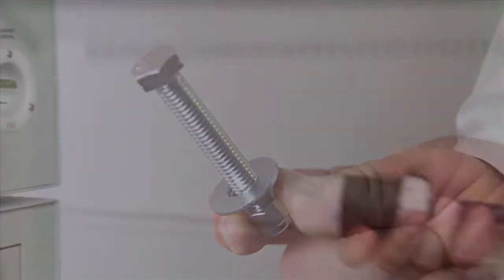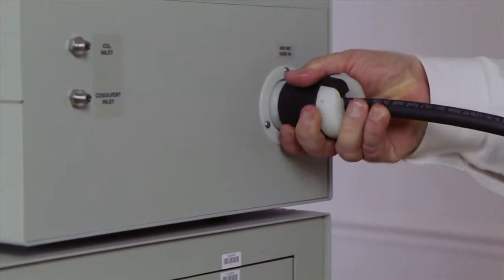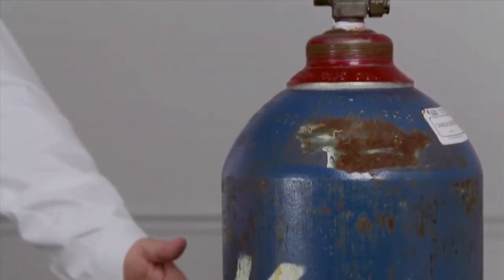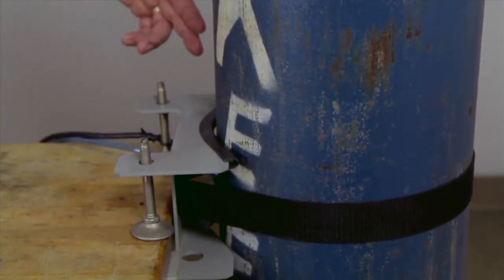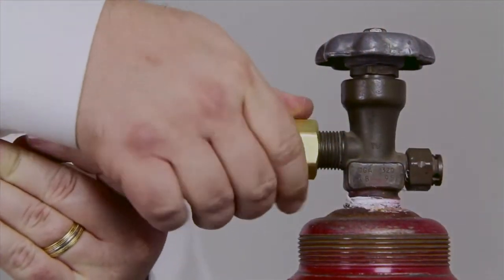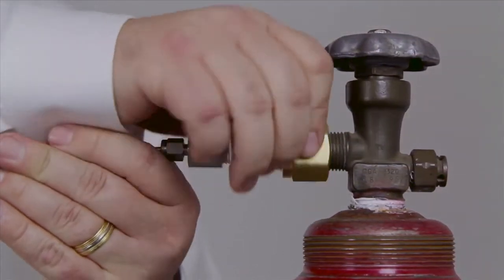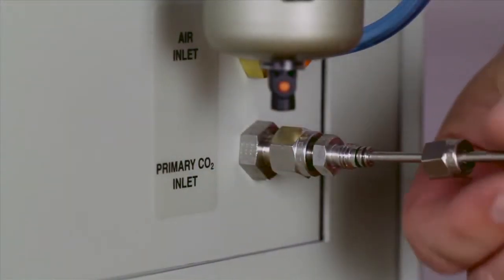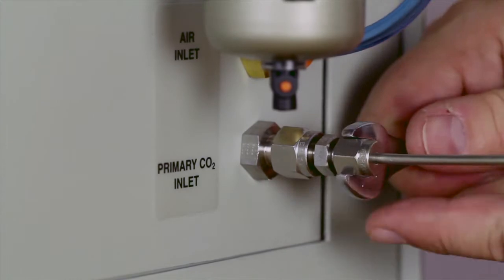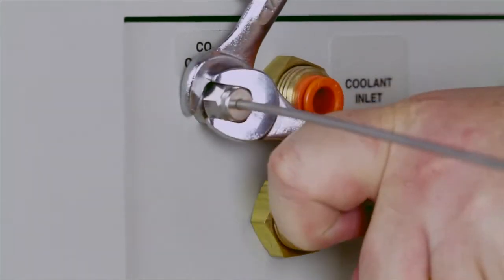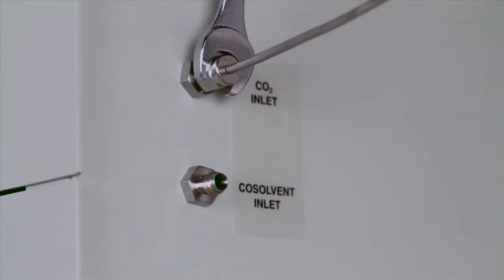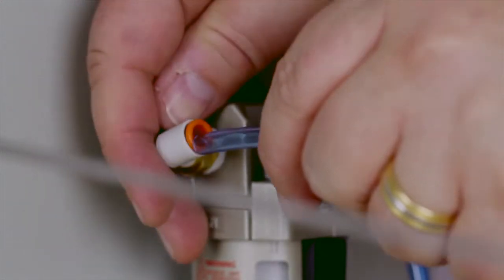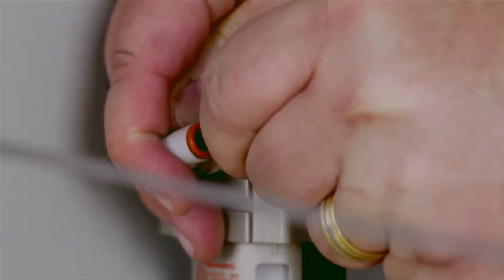Setup of the equipment. The SFT-150 is placed on a sturdy bench and bolted in place. Make the electrical connections to the SFT-150. The CO2 tank must be secured to the bench with an appropriate clamp. Connect the CO2 line to the CO2 tank as shown here. The other end is connected to the CO2 inlet on the back of the SFT-150. Connect the CO2 outlet on the pump drawer to the CO2 inlet in the oven cabinet using the length of 1/8 inch tubing provided. Connect the compressed air lines, pressing the tube firmly into place as demonstrated.